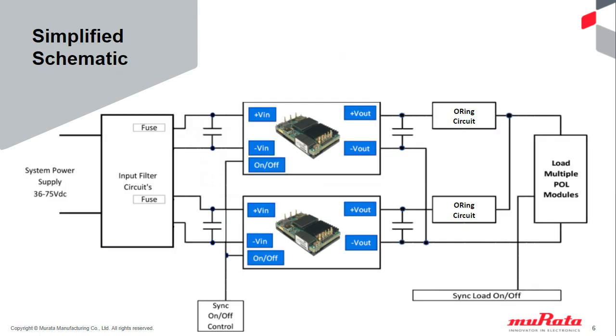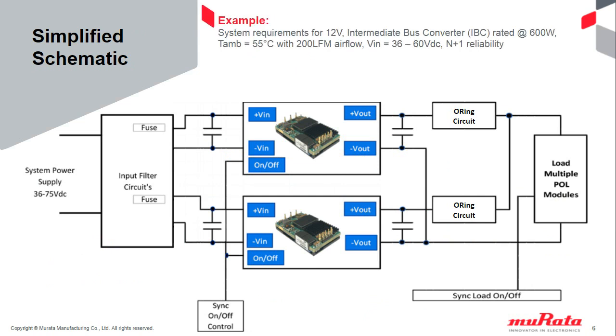So here's a simplified schematic for discussion purposes. Going forward, we're going to be talking about an example where we need a 12-volt intermediate bus rated at 600 watts at 55 degrees C with 200 linear feet per minute airflow. The input range is 36 to 60 volts, and we need an N+1 reliable system. First thing we want to talk about is what is an intermediate bus converter? Well, you have the main input power source, which we discussed before, coming from a diesel generator and a battery backup system. The intermediate bus is all of this circuitry, with the heart of the system being the board mount power supplies.